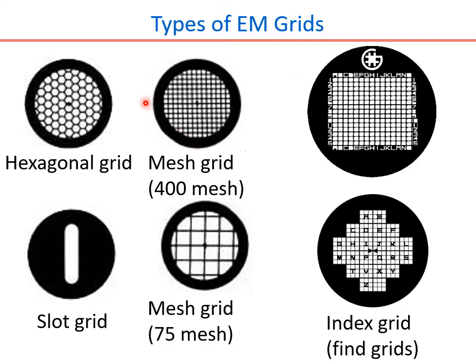If you are recording an electron microscope experiment, usually you move from left to right, and once you reach the end of the row, you make a translation here, reset to the left part, and again scan the surface. In that experience, if you start from here and keep moving, you will encounter a grid surface, then a grid bar, then a grid surface, then a grid bar. But take note, the grid bar comes only for a transient time and you just move along without much interruption. Let us see how this goes when you use the hexagonal grid.